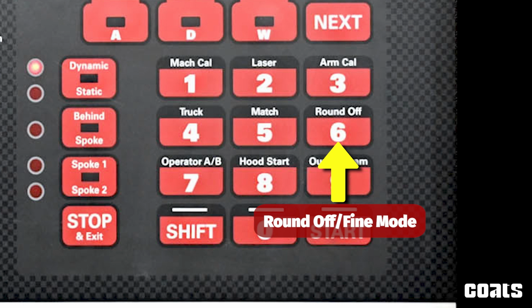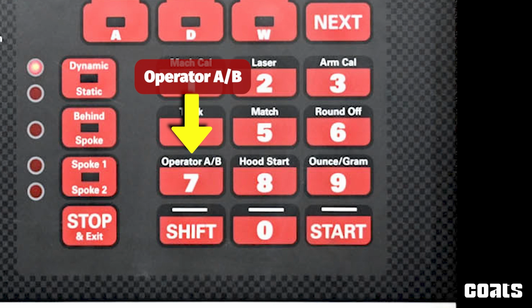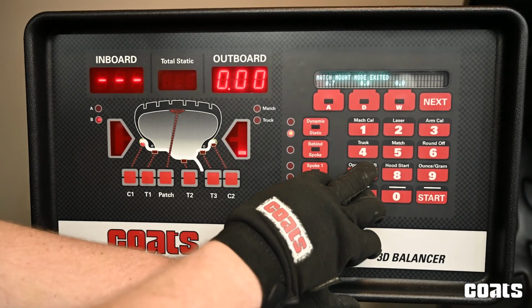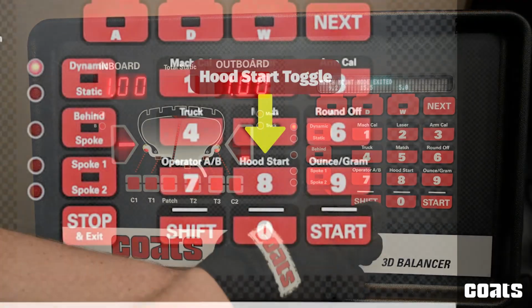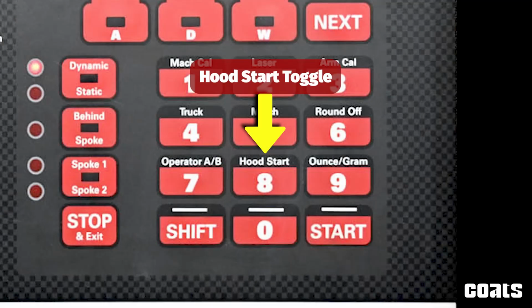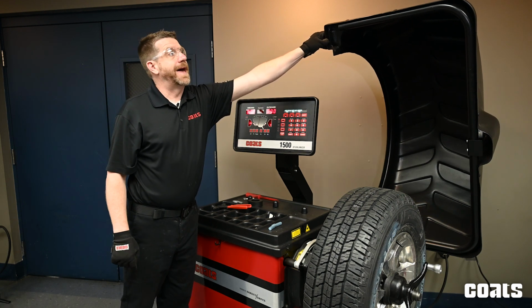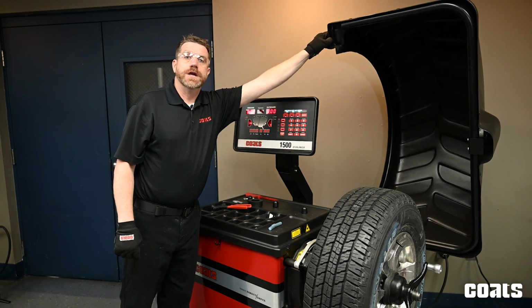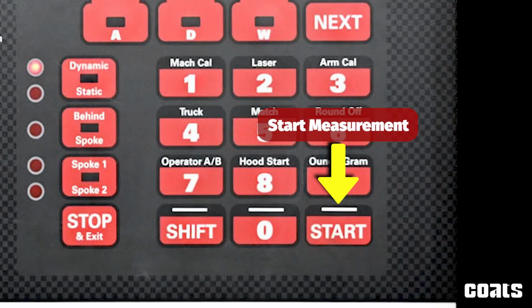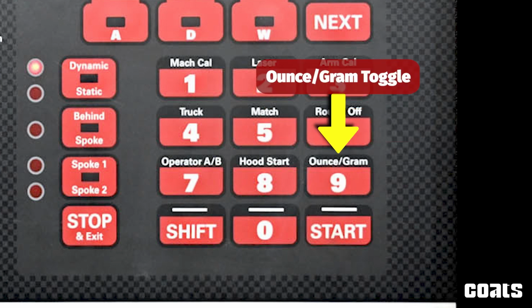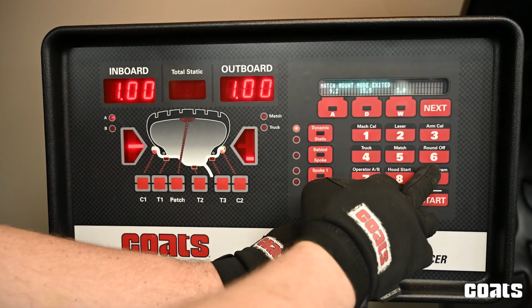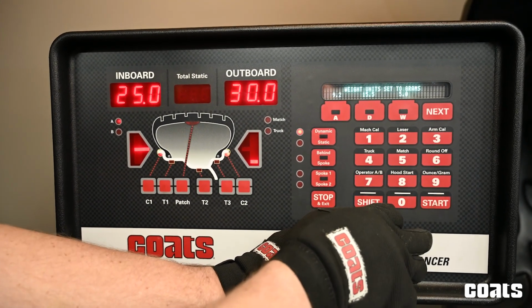Changing the balancer into the fine mode or round off, you can simply hit shift and round off and that will put the balancer into fine mode. Operator A and B allows you to toggle between operator A and operator B. Hood start, when you hit shift and hood start, that allows you to turn off or on the function that automatically starts the balancer when you close the hood. If you turn that off, you'll have to hit the start button in order to initiate a measurement cycle with the balancer. Shift and ounce grams simply changes the display from displaying in ounces or displaying in grams.